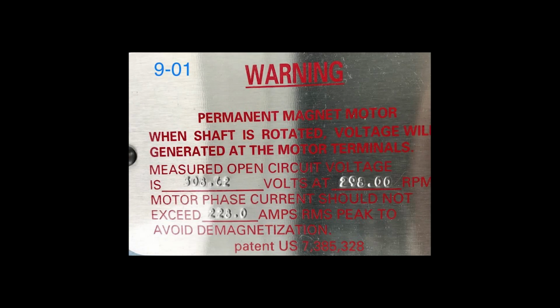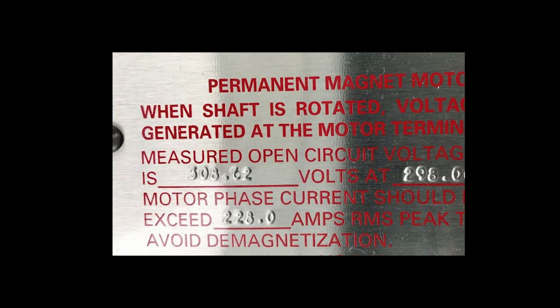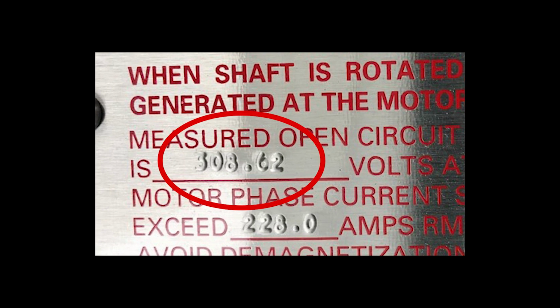Once you ensure the power is safely locked out, it's time to gather the information you'll need to set proper wiring. First, find the warning label on the Enduradrive motor. You'll need the EMF voltage number stamped on the label. Write down the EMF number on a piece of paper. We recommend also taking a picture of the label for later reference during the setup process.